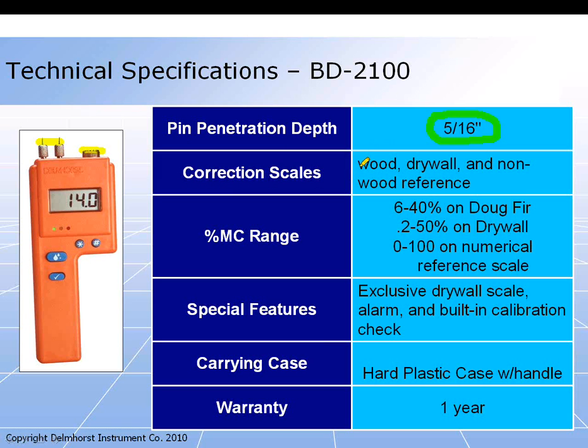One of the nice features about the BD2100 is it has different scales. So again, it's only a pin meter, but it offers you a wood scale that reads from 6 to 40% on Douglas fir. And again, if you're using this on other wood materials, there is a correction chart that you can refer to, to adjust the reading on screen to the actual moisture content. Another very nice feature, and this is, again, a Delmhorst exclusive, is it has a drywall scale. So on the Tech Check, we talked about using those readings on drywall as relative readings. The BD2100 actually gives you a percentage readout on drywall, and it goes from 0.2 to 50%.